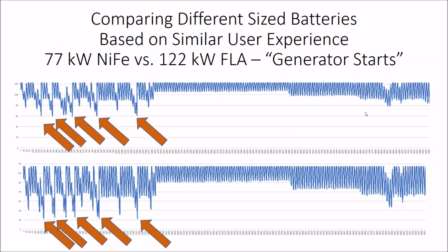What I really wanted to say was we were able to hone in on around an 80 kilowatt hour, or really 77 kilowatt hour, nickel iron battery bank. We honed in on that size because that was where it exhibited the same kind of generator usage as the larger lead acid bank.